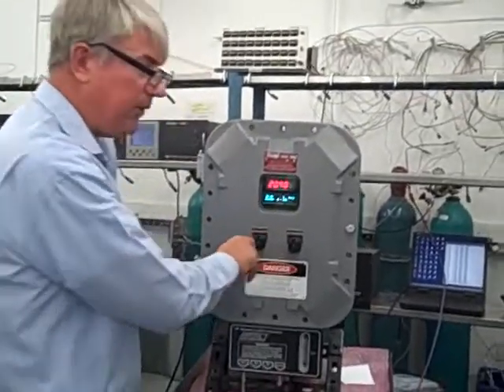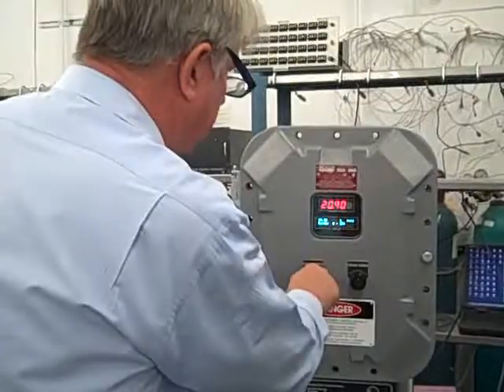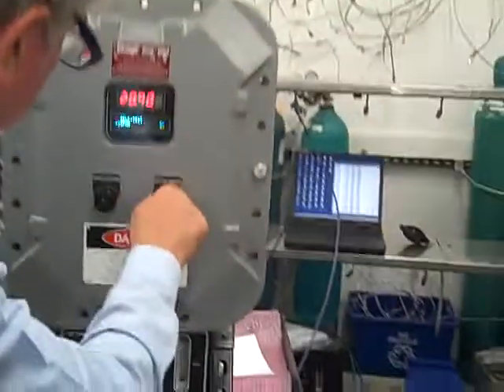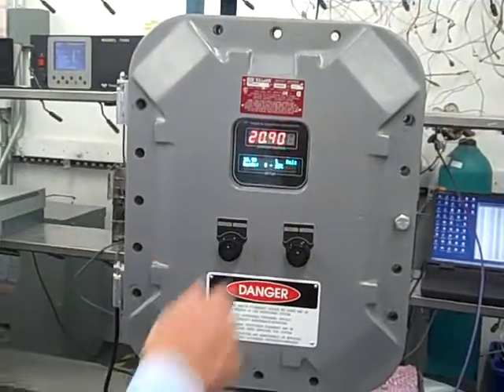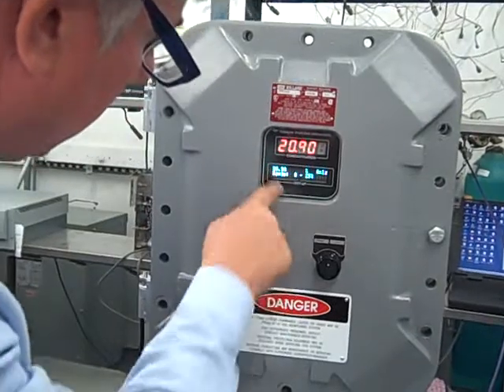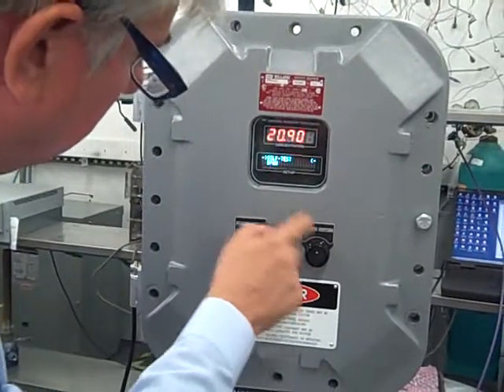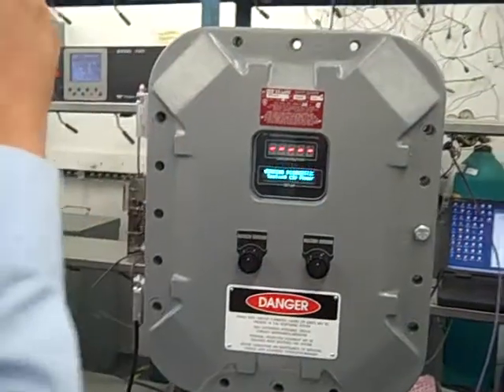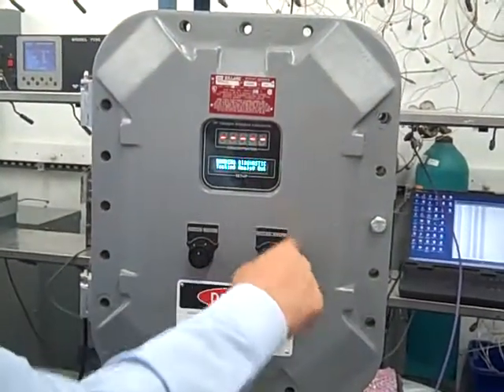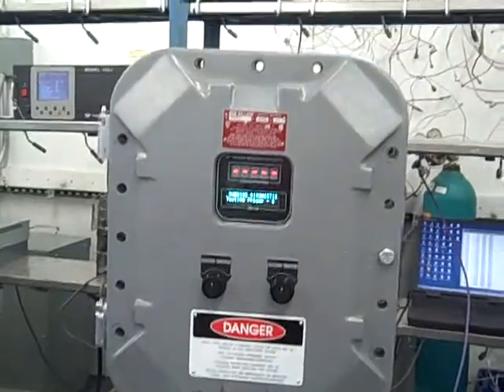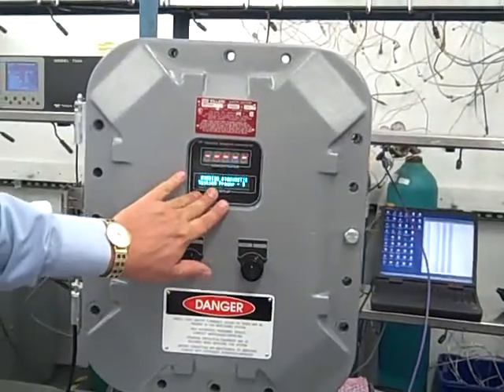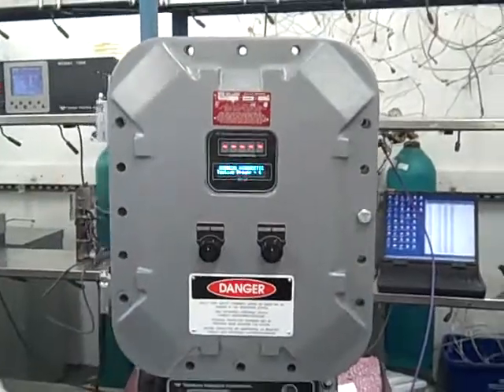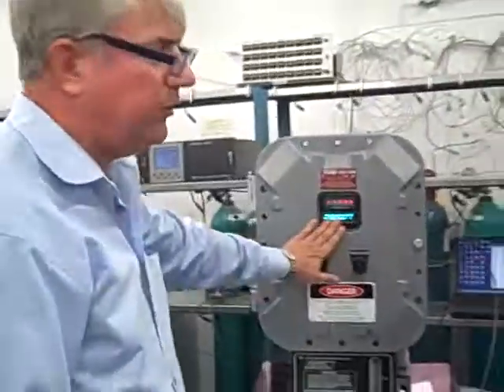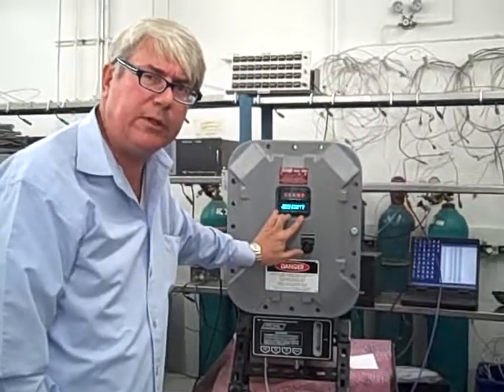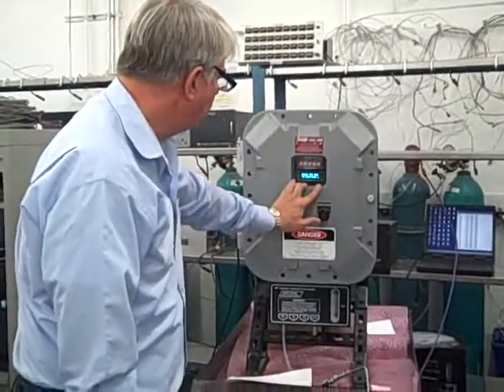Okay, so let's see the other features in here. Also, the other thing you can do is do a self-test. Now, if you have any question about the unit, you can go to the self-test mode. Notice what happens here. You select the menu option with the enter key, and then you accept it, and now it's running the self-test. To scroll up and down through the menus, you use the up and down keys. Now what this is doing is testing the preamp, testing the outputs, testing the power supplies to make sure all of those are good. And how long does this take? About 3 or 4 minutes, something like that? It takes about that long.